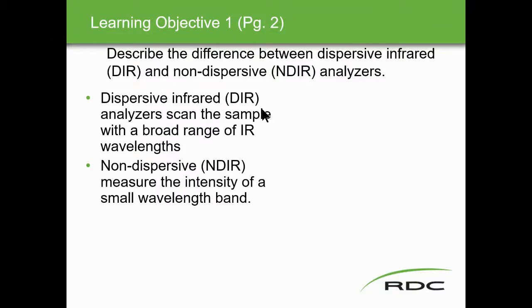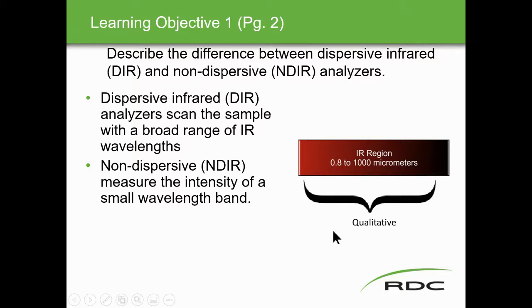Learning objective one: describe the difference between dispersive infrared and non-dispersive. Dispersive analyzers scan the sample with a broad range of IR wavelengths, while non-dispersive analyzers measure the intensity of a small wavelength band. The IR region according to our spectrum is 0.8 to 1000 micrometers.